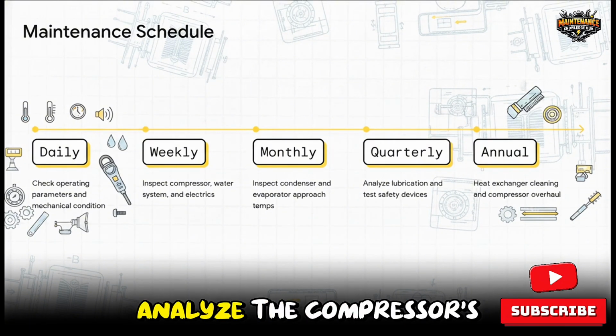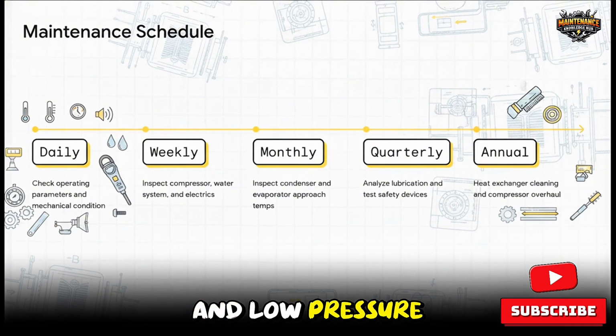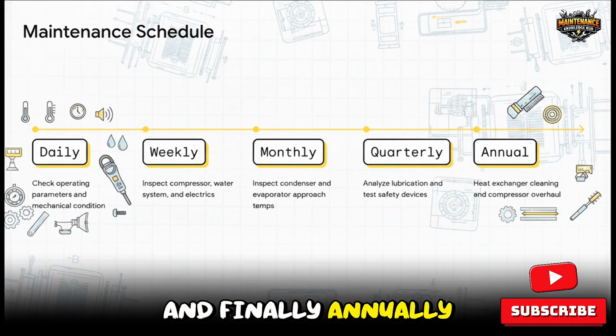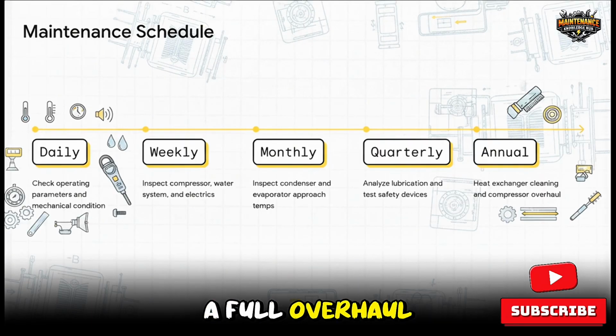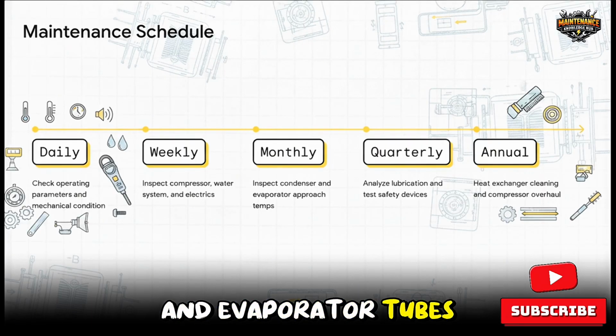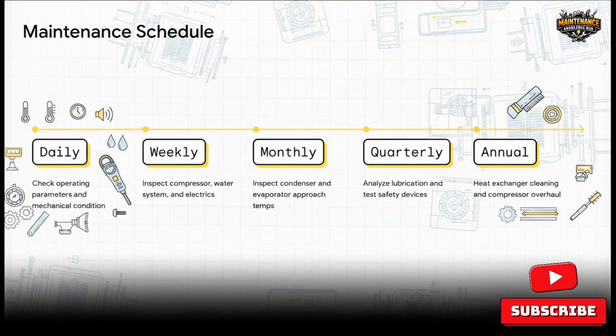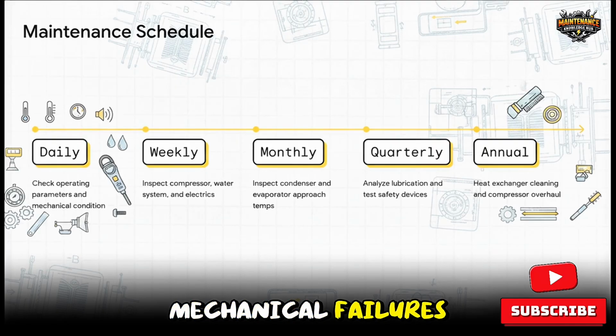Quarterly, it's time to analyze the compressor's oil condition and test high and low pressure safety switches. And finally, annually, the system gets a full overhaul, mechanically cleaning the condenser and evaporator tubes, checking bearings, and calibrating all sensors. It's dense, for sure, but this consistent care is what prevents catastrophic mechanical failures.